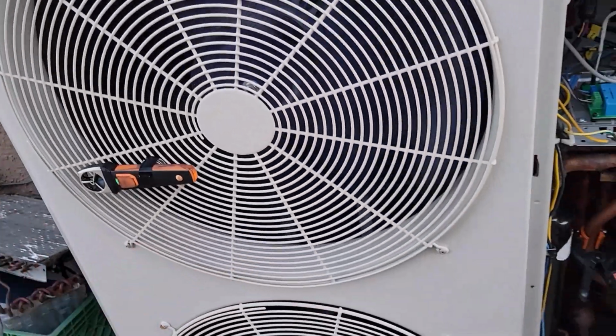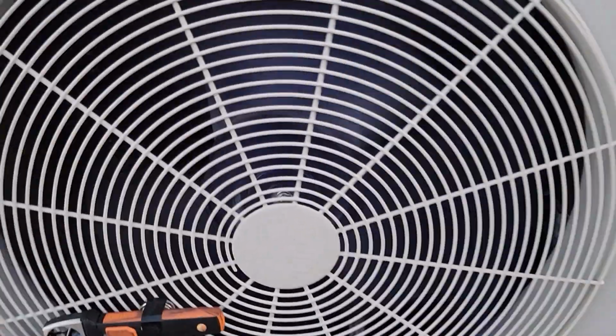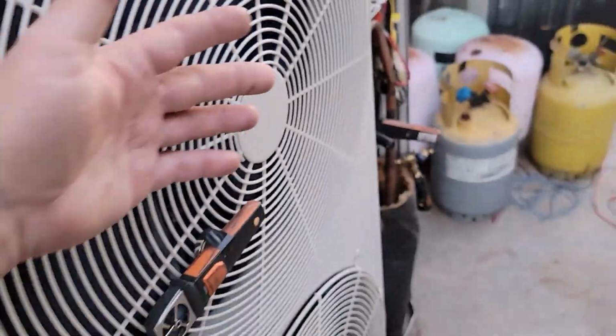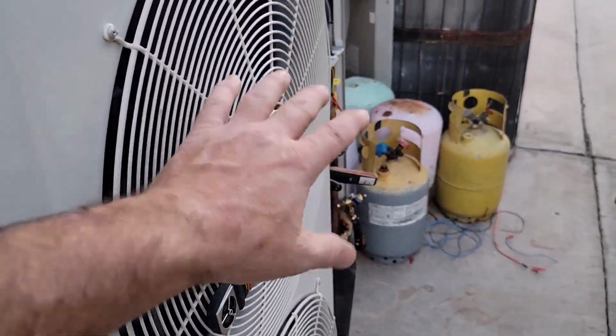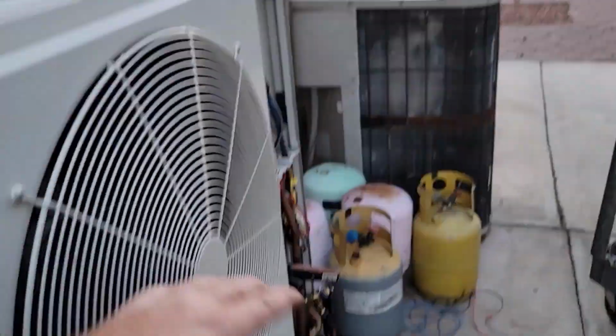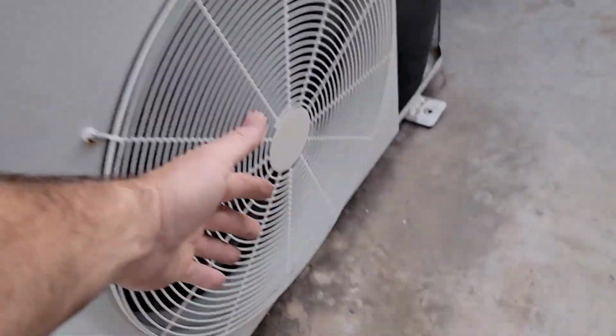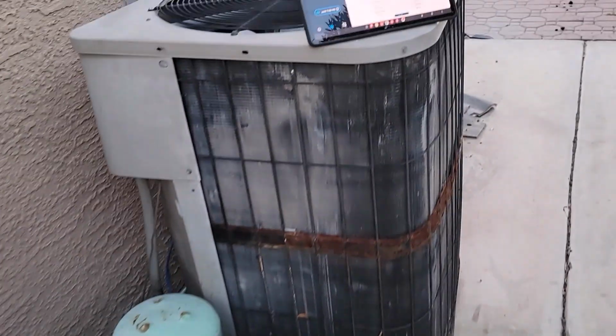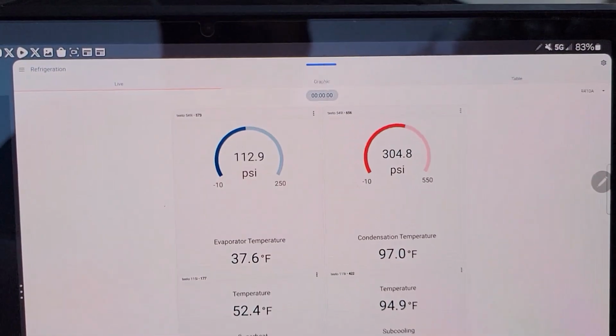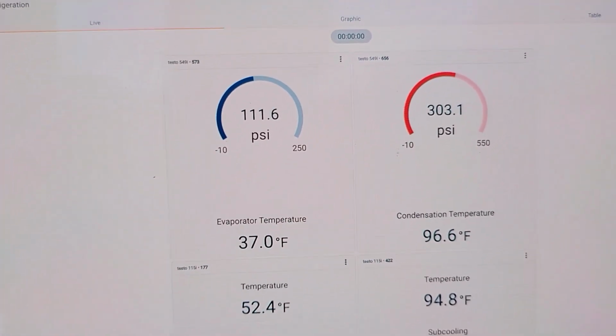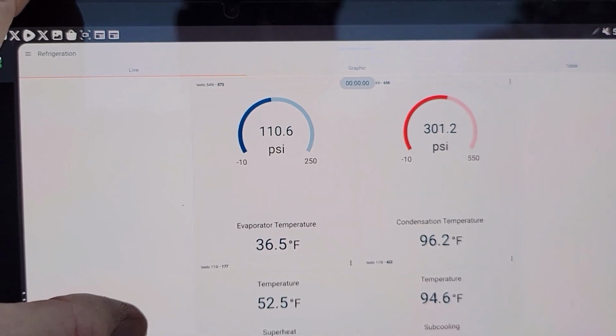That's probably about right, because there's two fans. I mean, it's blowing air pretty decent, but the thing is, you're used to how much blows out of one fan that size, and there's only a 3-ton unit. It's actually got two of them. And I'm sure the pressure's tanking. Oh yeah, see that? Down there. It's dropping like a rock.